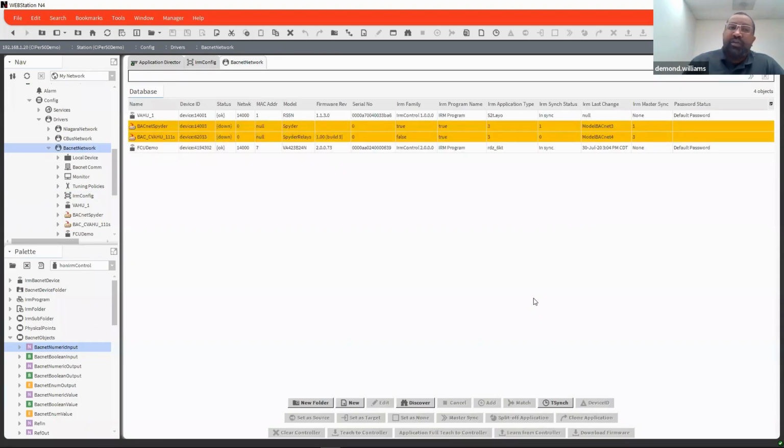If you power the controller off and hold that service button down for about 10 to 15 seconds and then let it go, it actually does a factory reset, where it wipes the controller and puts it back to factory default. So that is another nice little feature.